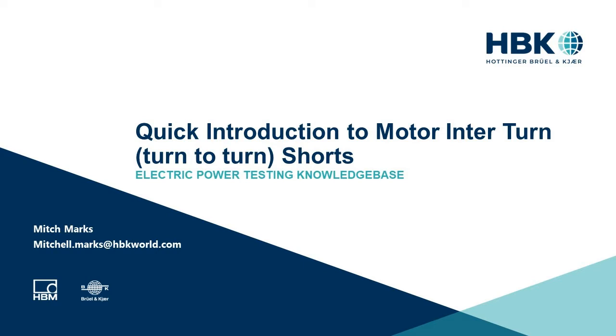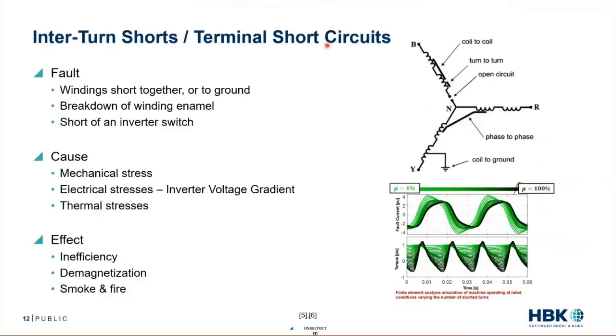That covers bearing currents, inter-turn shorts, and terminal short circuits. As introduced in the previous slide, this is an electrical diagram of a three-phase motor with a neutral. We can have a variety of short circuits: coil-to-coil shorts where the lamination between two windings shorts together, turn-to-turn shorts where the fault happens between coils, phase-to-phase shorts where phase A and phase B get shorted together, coil-to-ground where the copper winding shorts to the stator housing or laminations, and open circuits where they're not touching at all.